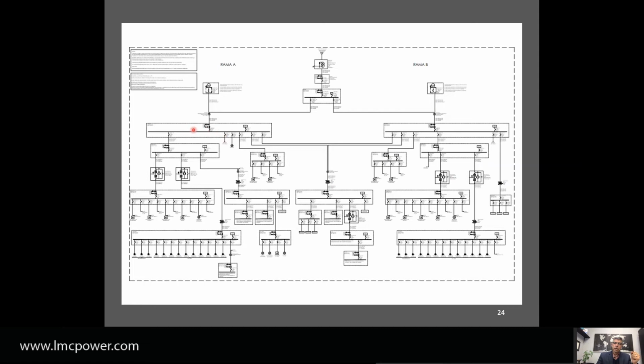Then from there, we go to another panel. This looks very close, but there are distances between these panels. This panel feeds two large UPSs, each about $30,000 to $50,000 - some over $100,000. So they want to protect the input of the UPS with a 200 kA surge protector.